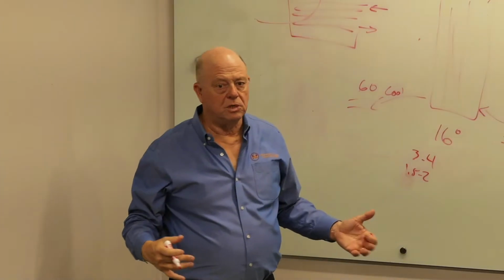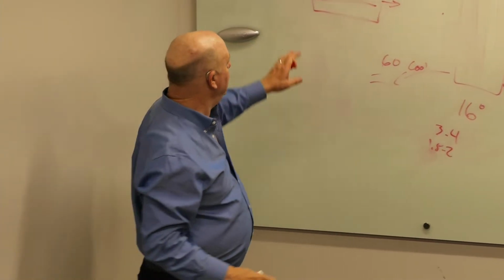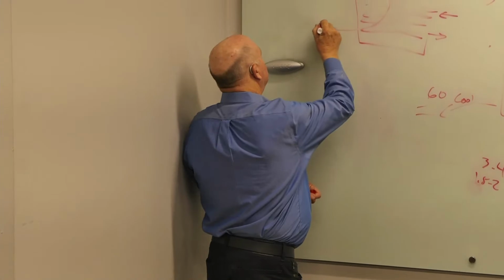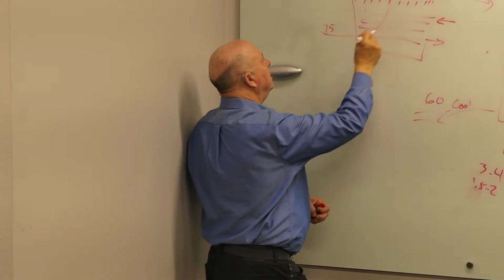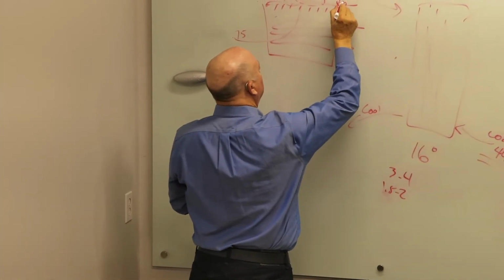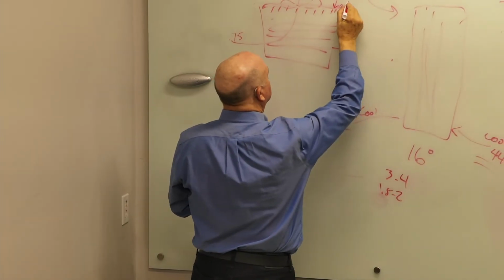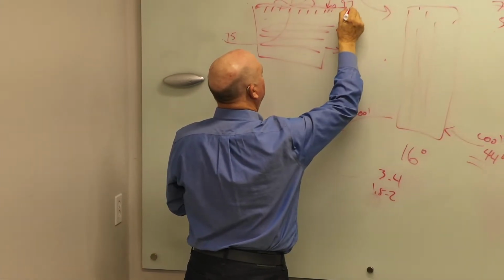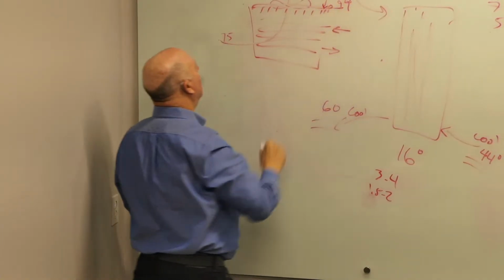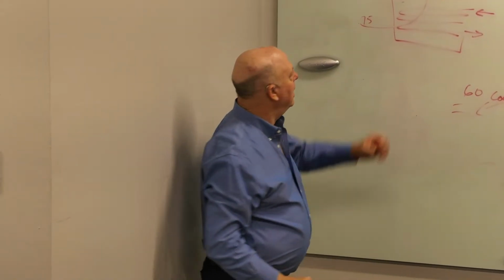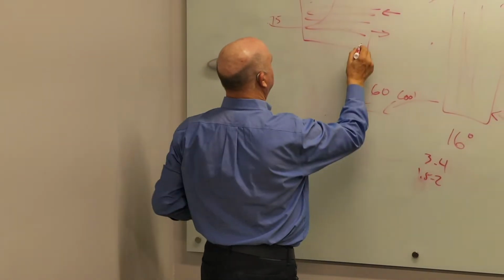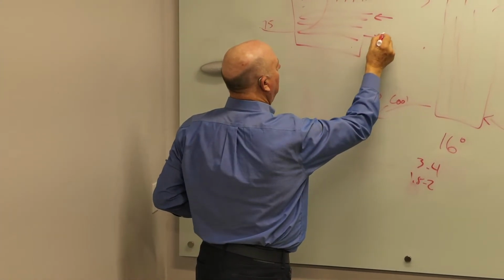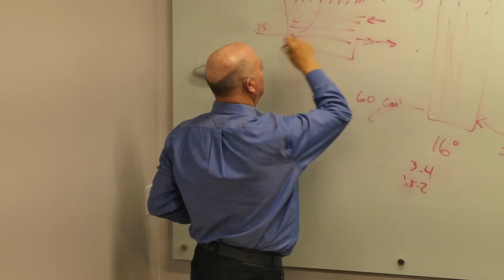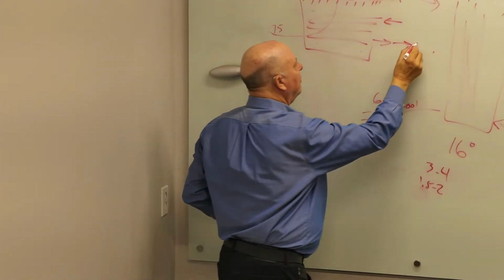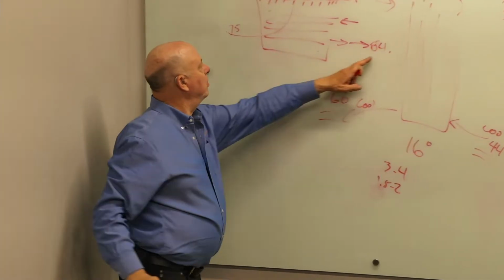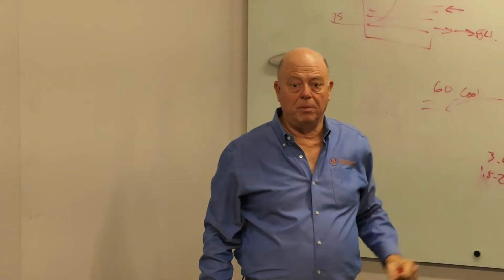Air's a fluid, just like water's a fluid. And the approach would be, if this is 75 wet bulb outside, and I'm dumping 94-degree water in the top, and I'm able to make, let's just say, 84-degree water coming out of here, then the approach would be 84 minus 75 wet bulb, 9 degrees.